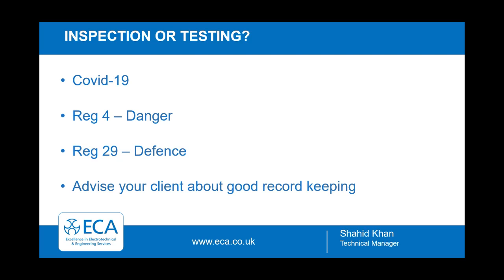The last couple of bullet points were only recently added to the presentation following a query that came through on the helpline where a member was finding it difficult to explain to non-technical clients the need for periodics. They were under the impression that perhaps this was an optional activity rather than something that really is mandatory. Regulation 4 of the Electricity at Work Regulations mentions that all electrical systems must be maintained so as to prevent danger. And Regulation 29 of the same statutory document effectively calls for the duty holder to provide their own defence.